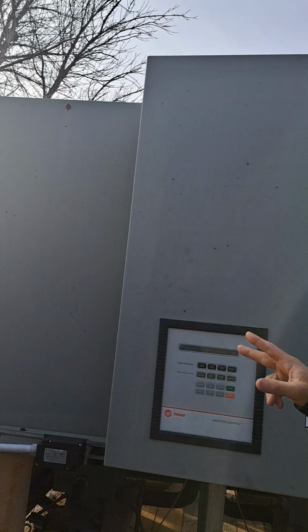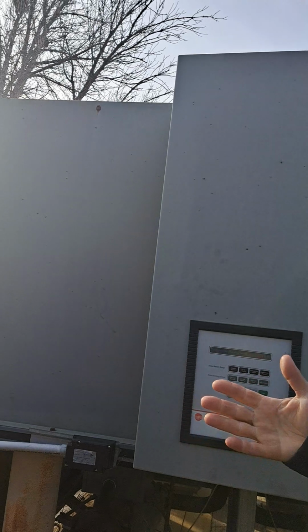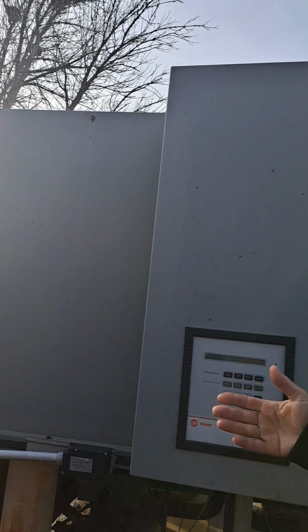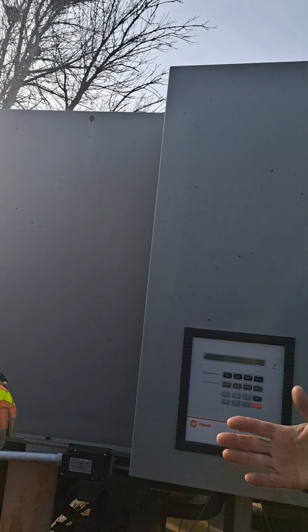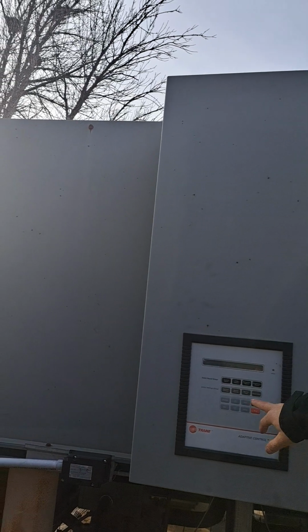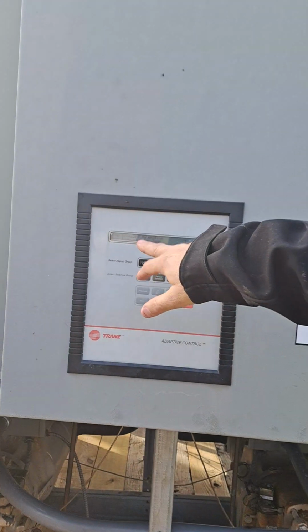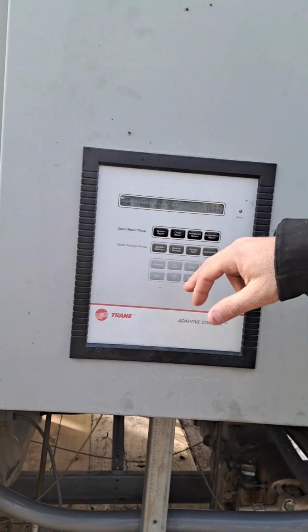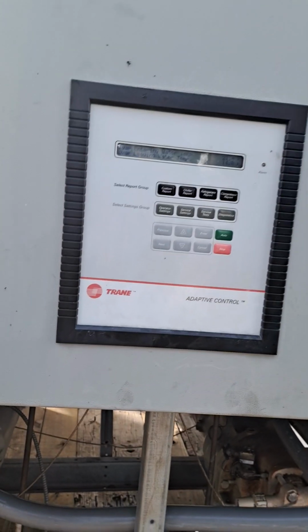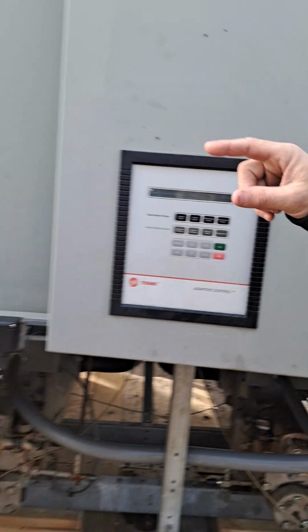There's different types of alarms. There's non-latching and there's latching. A non-latching alarm, when whatever caused the alarm clears, whatever fault clears, it'll automatically restart. If it has major faults, it'll actually lock out the circuit and it'll require a manual reset. So you'll have to go through the diagnostics menu and it'll tell you what to do to reset it. On the screen, it says hit enter to clear faults. So you'll just go through the screen and do that.